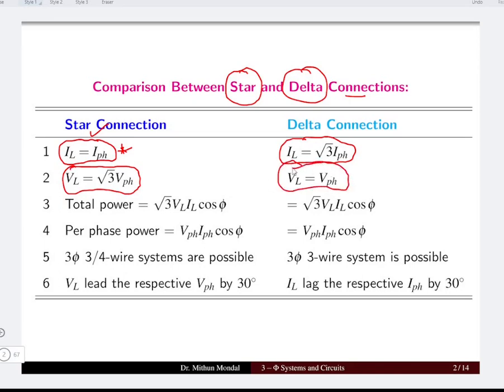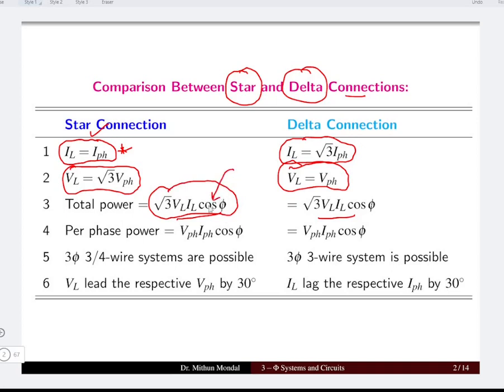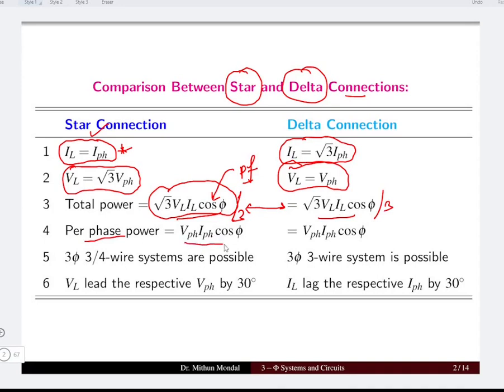The line voltage in the star connected network is root 3 times the phase voltage, whereas the line voltage in the delta connection is equal to the phase voltage. The total power in the star or delta connected system remains the same, calculated as root 3 times the line voltage multiplied with line current multiplied with the power factor (cos φ). For a balanced system, the per phase power is total power divided by 3.